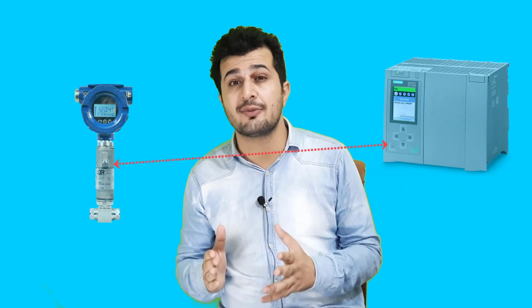When we talk about the history of Modbus and how it came into the picture, protocols like Modbus and Profibus got into the picture because before them, every instrument that needed to be connected to the controller required a dedicated wire. That means if you have thousands of pieces of equipment, you need thousands of wires going into your control system. That's very costly and very difficult to troubleshoot.